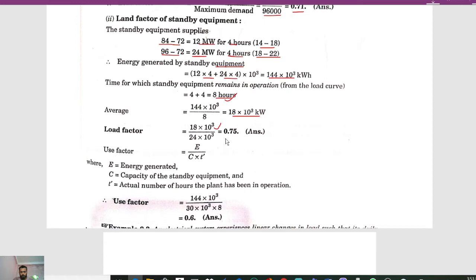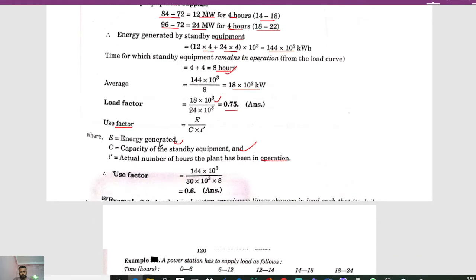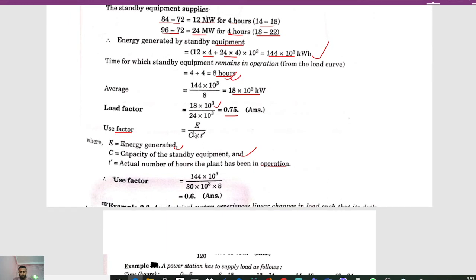To calculate the use factor, the formula is e / (c × t), where e is energy generated, c is the capacity of the standby equipment, and t is the actual number of hours the plant has been in operation. Energy generated by standby equipment is 144 × 10³ kilowatt hours, capacity c is 30 megawatt (30 × 10³ kilowatt), and time t is 8 hours. Use factor = 144 × 10³ / (30 × 10³ × 8) = 0.6.